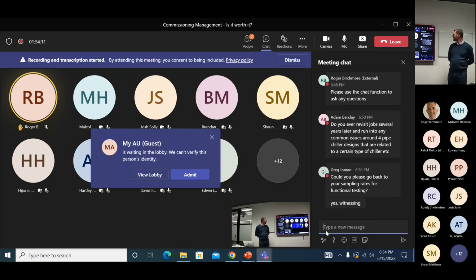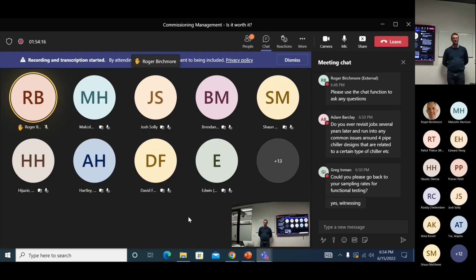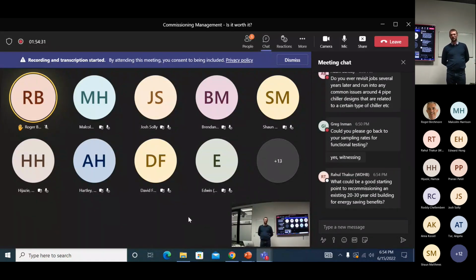4-pipe chillers - they're really complex, for a number of reasons. They look great on paper, great from an energy saving point of view. But often to get the right conditions so you actually get the energy saving, it's probably only a small percentage of the actual operating hours. Outside of those hours, it's suboptimal - the chiller is either struggling or you're not providing particularly good conditions, and they do break down. They're very complex to commission.